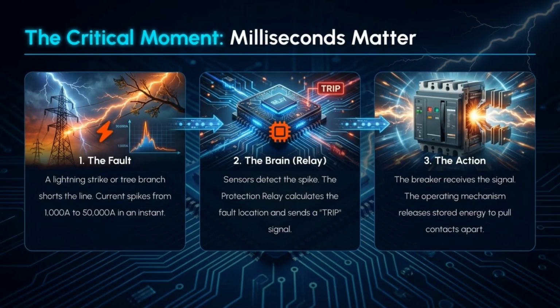In the critical moment, milliseconds matter. First, a fault occurs, causing current spikes up to 50,000 amps. Second, the protection relay, or the brain, calculates the fault location and sends a trip signal. Third, the breaker acts instantly, releasing stored energy to pull the contacts apart.